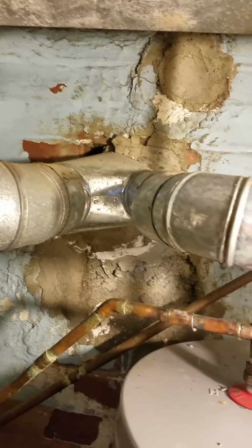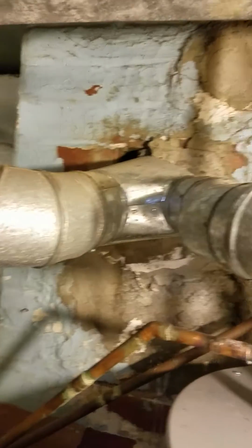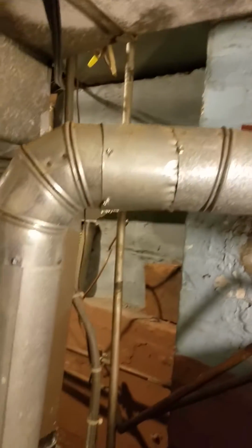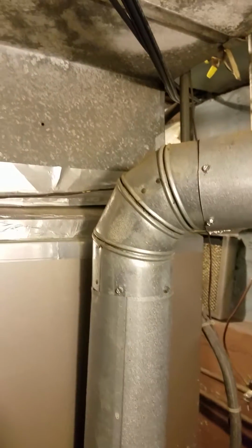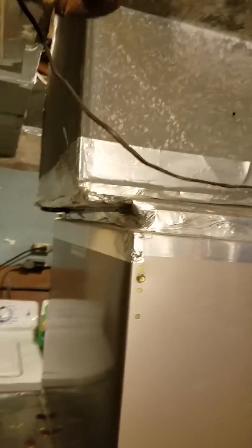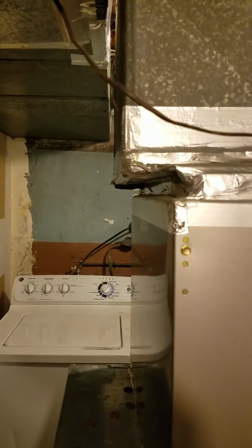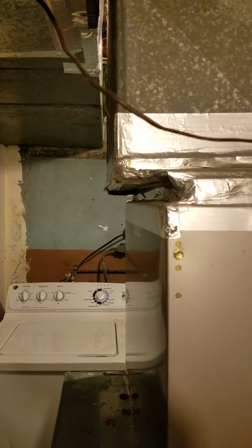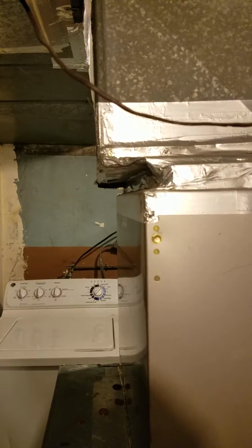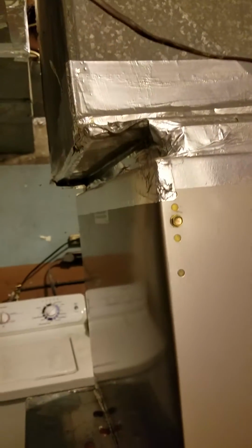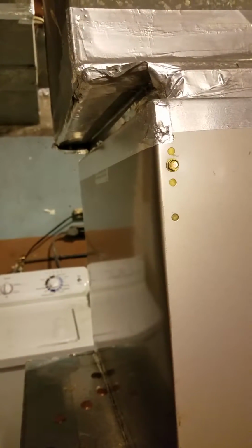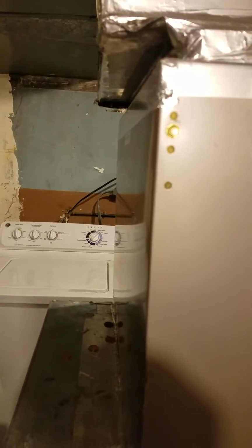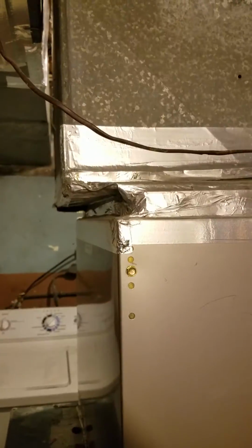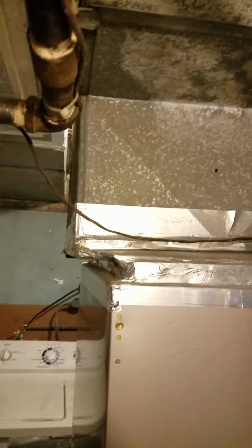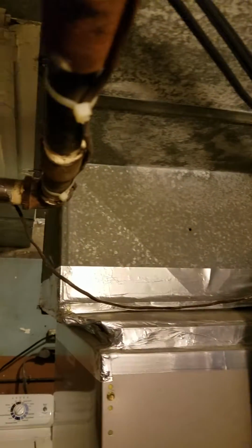The flue is a single-walled flue, and we have an offset chimney. You cannot get a liner down this, so we would have to cap this off right here and run the PVC out to the left-hand side, out to the side of the house. There's an offset right here on the top of the ductwork where the coil is not built up in there either, and that is about a 2-inch gap right there. You can see it right there, how that looks. So again, there's another overhang. So restriction there, restriction here, and needs to be built back into the current ductwork.